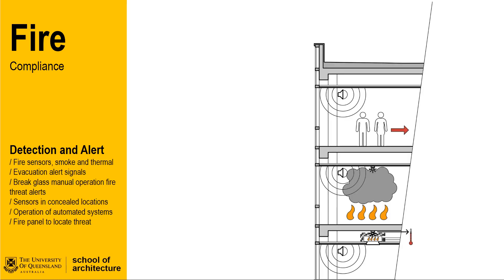The first key principle of fire design is the detection and alert of a fire threat. This is facilitated through a network of sensors that detect the potential presence of a fire through smoke or heat. In some instances, such as dusty environments like workshops and production facilities, a thermal-based detector may be used to prevent false alarms. Many detectors are focused on occupiable space, but depending on the type of building and the servicing strategy, there may be an almost equal number of detectors installed in inaccessible areas that have building services, equipment, and infrastructure installed.